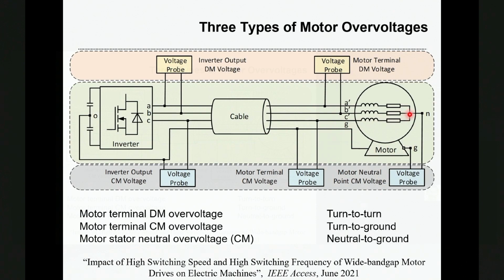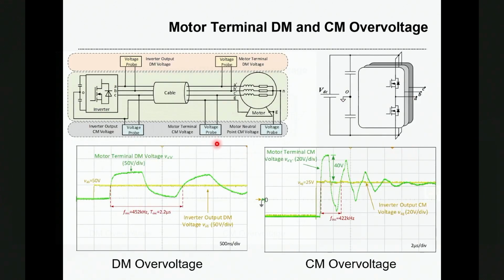And then there is a 3rd type of over voltage. That's the motor neutral over voltage. That's the common mode type of over voltage. You will see an over voltage at the motor stator winding neutral with respect to the ground. So we have demonstrated this in experiments. For example, this one shows the motor terminal differential mode over voltage, where the green trace is the motor terminal phase-to-phase voltage, and the yellow one is the inverter output voltage. And this one shows the motor terminal common mode over voltage, and the green one is the motor terminal voltage, and the yellow one again is the inverter output voltage.